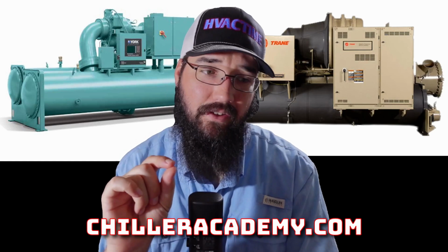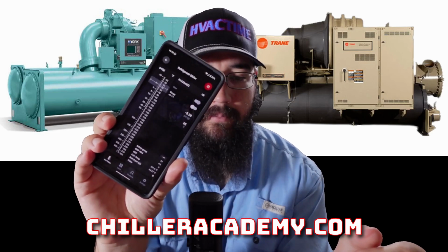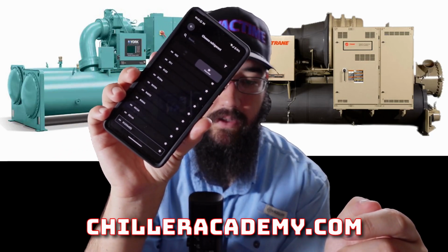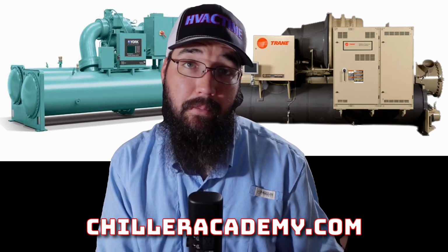One app I would highly recommend is RefTool by Danfoss. It is a fantastic app. I've used it for years and years, and they've only made it better over time. But that is this one here. So this is RefTool, an incredible system. Highly recommend. And you can go in and save all your favorite refrigerants. If you're not familiar with this, I've got that whole list I just detailed out there inside of there. I can't promote that app enough. It is extremely useful. And especially if you're in that situation where you're trying to switch back and forth between PSIG and PSIA, it is actually really easy to do that instead of trying to run conversions and stuff or do math in my head that I'm not very good at to begin with. Using that as an in-between measure helps a lot.